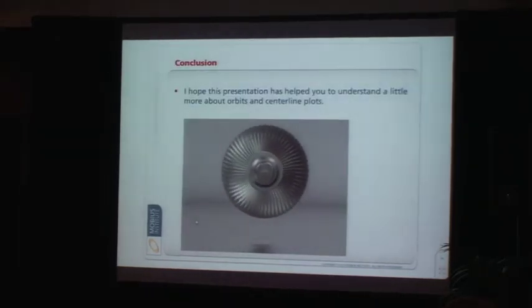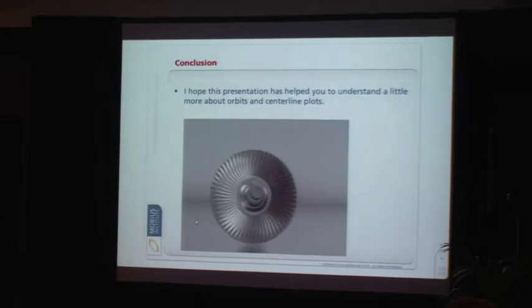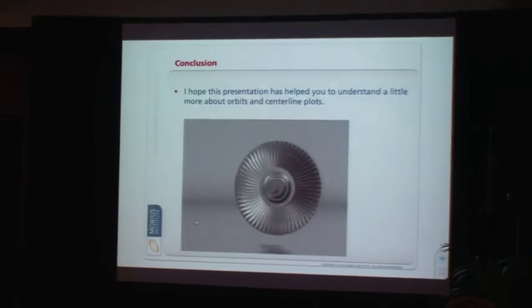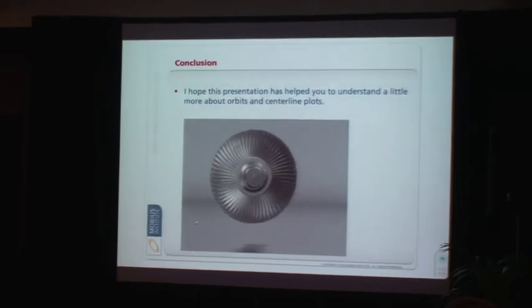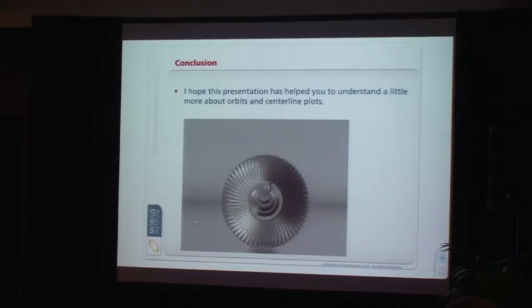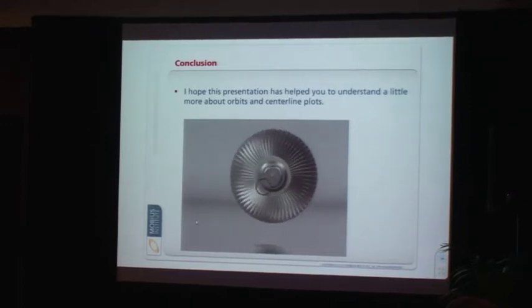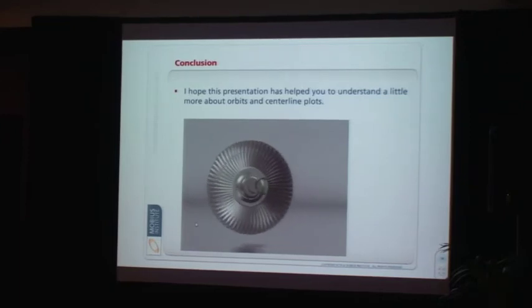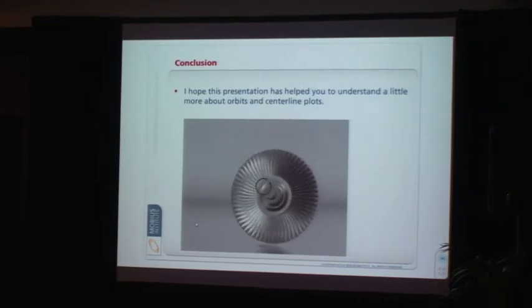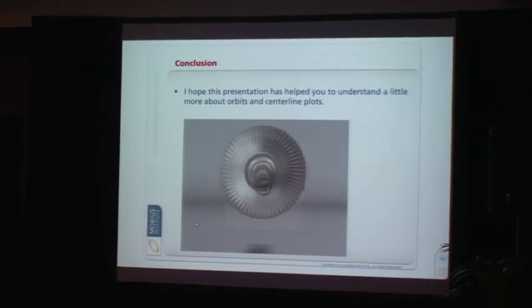Anyway, we could talk about that a lot more, but we can go through and model all this stuff if we like, or we can look at the data and just see what's going on. Bottom line is, using the two prox probes and the Keyphasor, we can tell how the shaft is moving, where it's moving inside the bearing, and therefore understand if we've got any mechanical issues like unbalance or misalignment, or if we've got existing or potential stability issues as well.